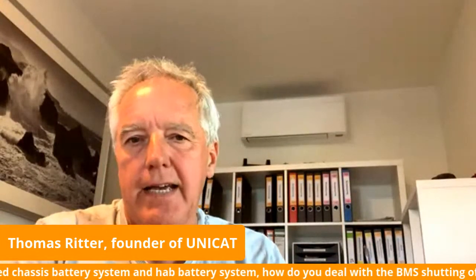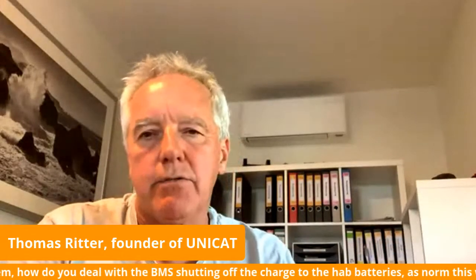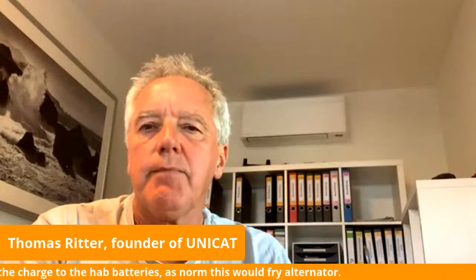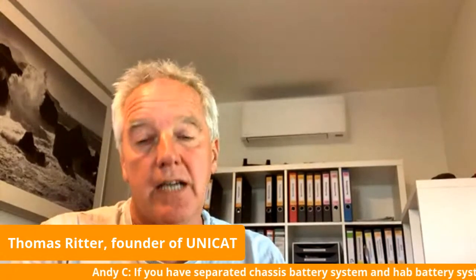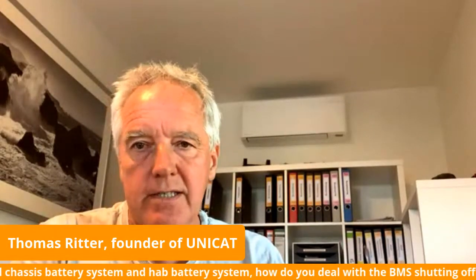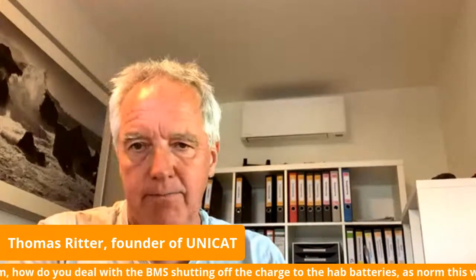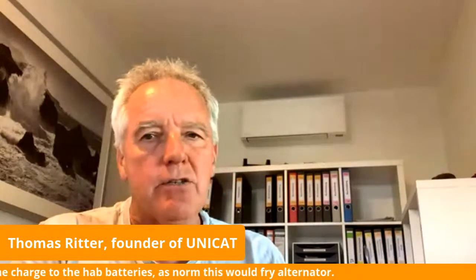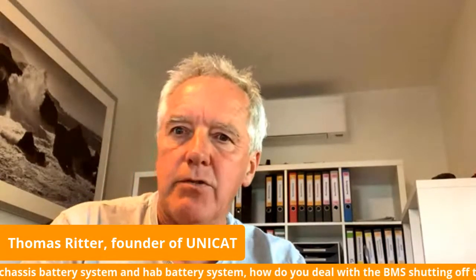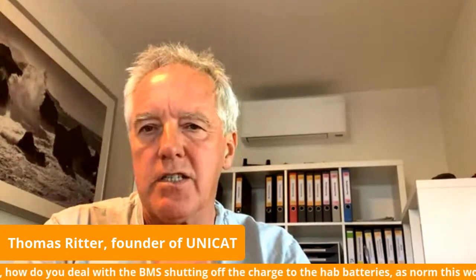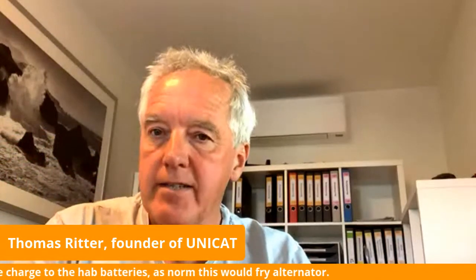As said, you should have separate chassis batteries and body batteries anyway, so that's a good question. You only disconnect the batteries from charge in an emergency case with lithium batteries, because if lithium batteries get overcharged, they are dead. If you overcharge an AGM or lead acid battery, it gets warm and starts making gas, but it's not instantly dead. A lithium battery will be dead. That's why the battery management system, in the worst case, will disconnect the lithium battery from all sources of charge.